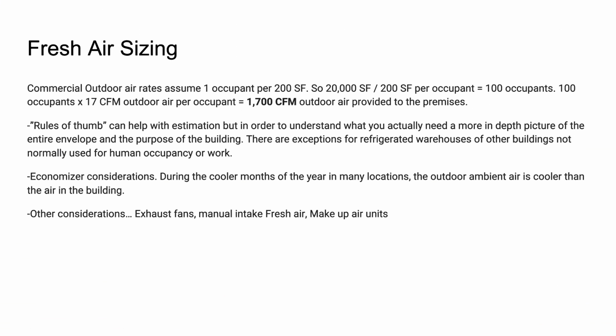Fresh air sizing - we bring this up because on RTUs, that's most typically how commercial spaces provide fresh air for the building. Every building, depending on occupancy, has different amounts of what they call air changes per hour - how much fresh air you have to bring in to ensure there isn't built-up stanky air. You got to turn that stank over - I think that's how it's said in the ASHRAE manual. You have to make sure that over a certain period of time, every bit of air in the building gets replaced with fresh air, so nothing undesirable builds up. That varies quite a bit, because a retail environment is completely different from something with gas cooking or a salon.